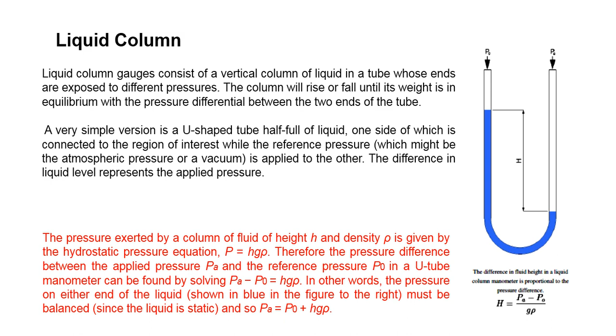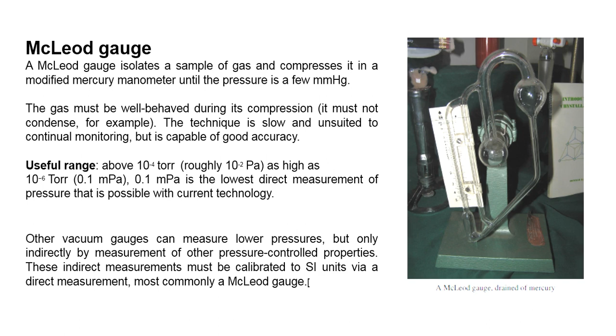McLeod gauge is another instrument which can be used to measure the pressure. It isolates a sample of pressure and compresses it in a modified mercury manometer. It is basically used to measure pressure which is a very few mm of Hg. The gas must be well behaved during its compression. The technique is slow, unsuited to continuous monitoring, and is capable of good accuracy. Normally, the range of measurement of pressure in this is from 10 raised to power minus 2 Pascal to 0.1 millipascal. Other vacuum gauges can measure low pressure, but only by indirect measurement.